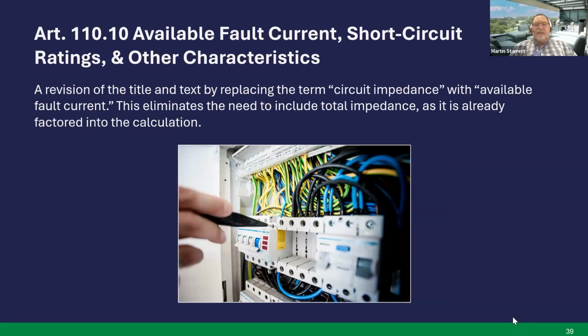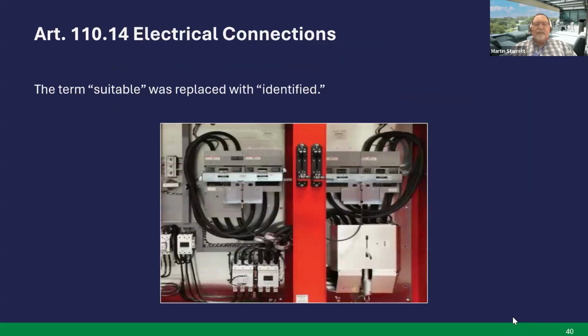110.10, available fault current, short circuit ratings, and other characteristics. A revision of the title and text, replacing the term circuit impedance with available fault current. This eliminates the need to include total impedance as it's already factored into the calculation. So there was no need to do it twice. That's why they removed it from the title and text. Next slide.